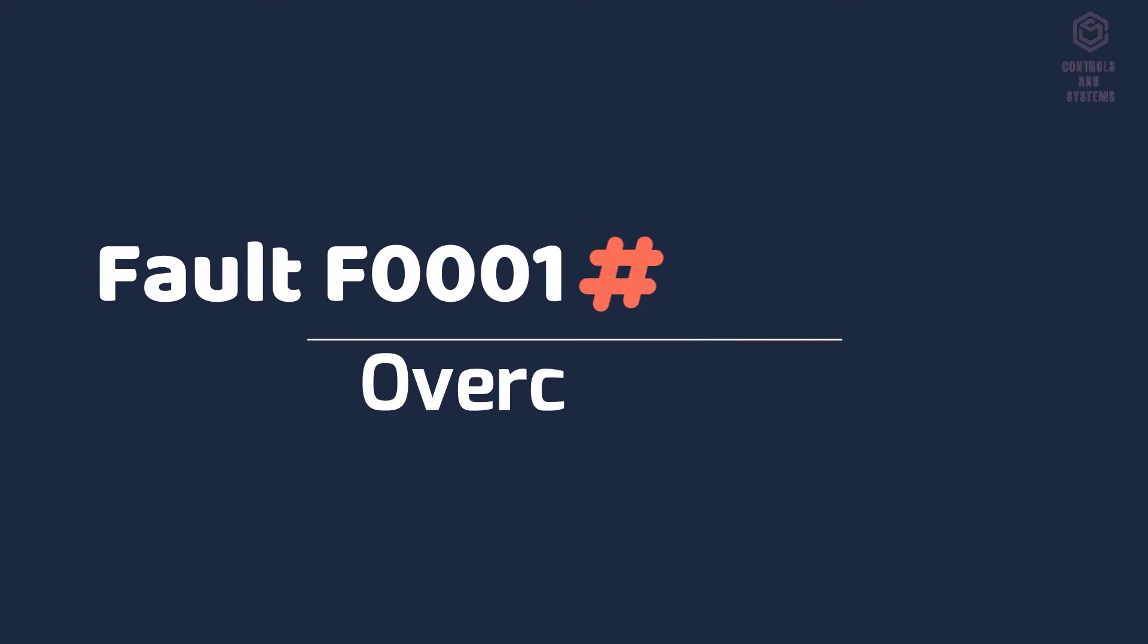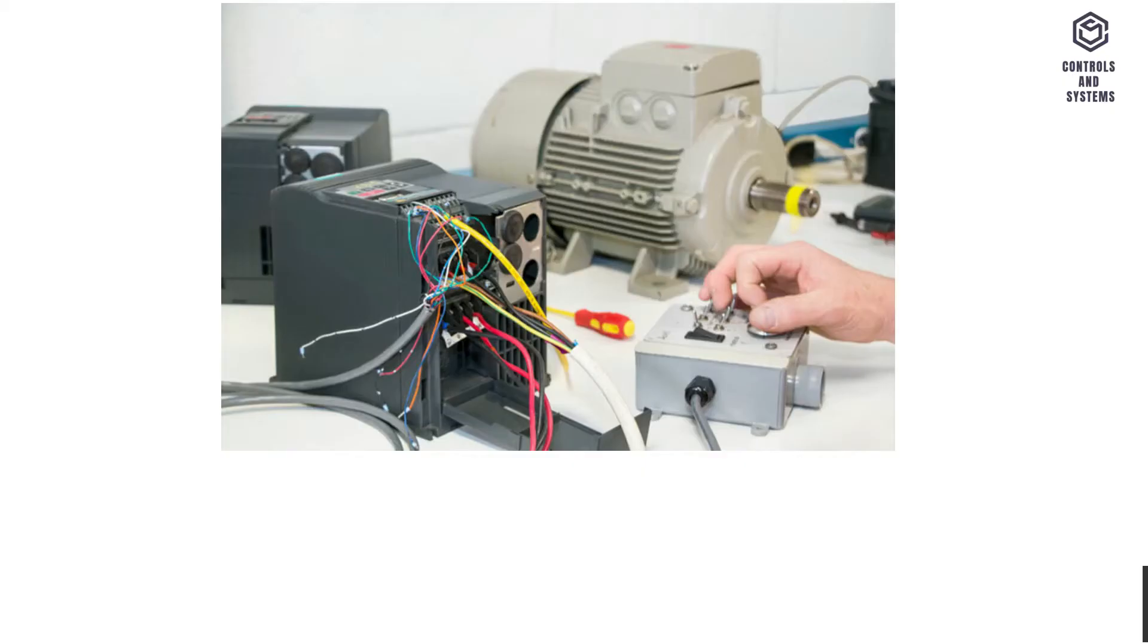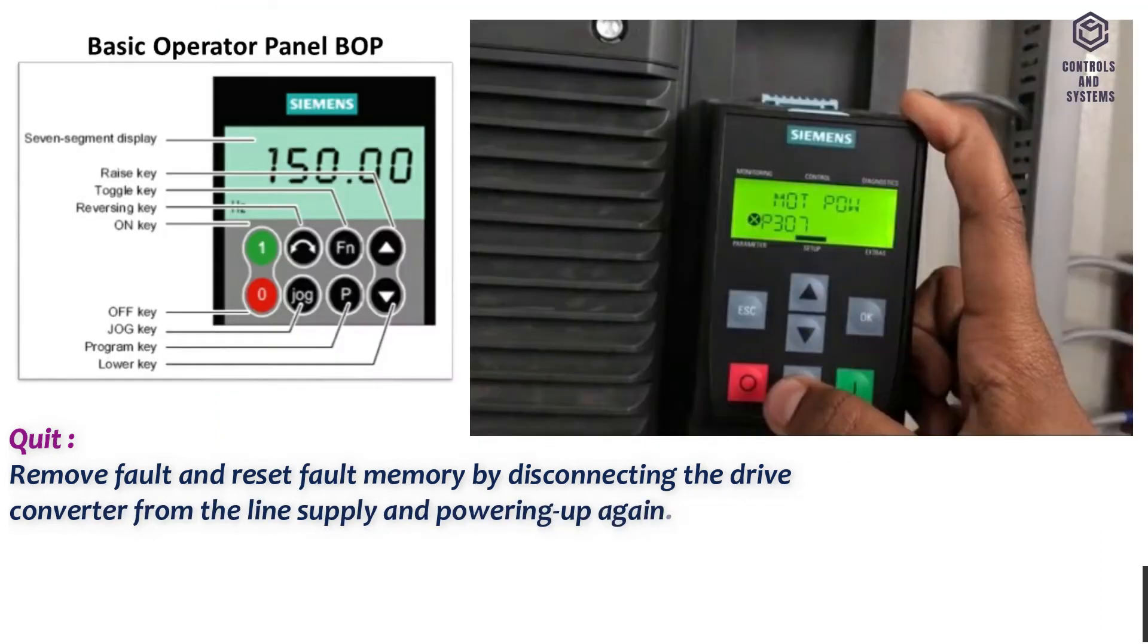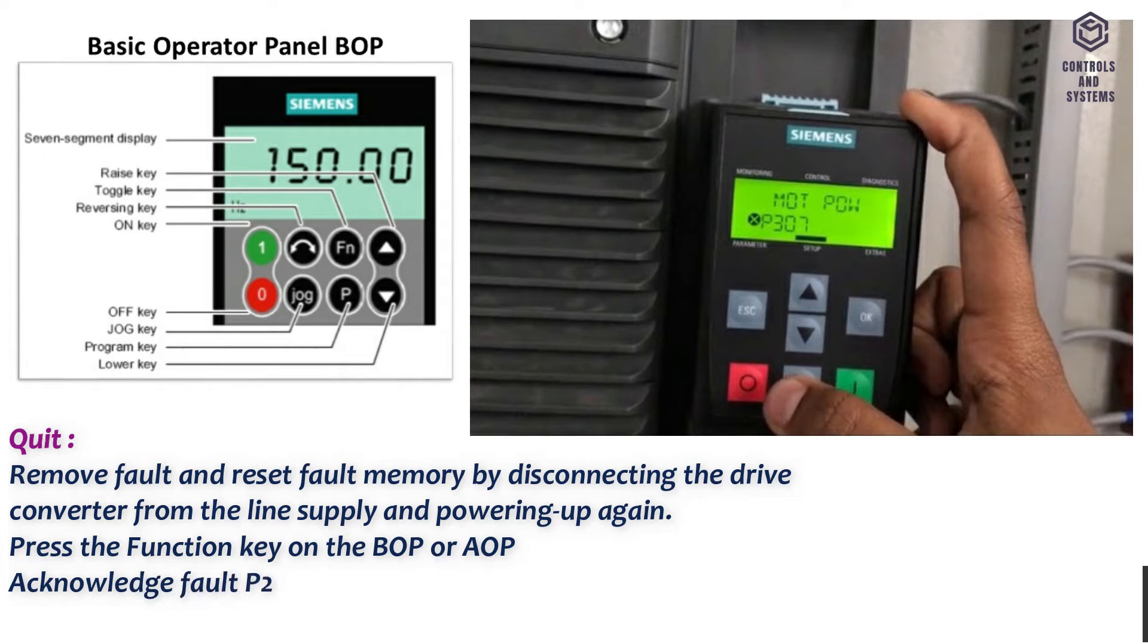Fault F0001, overcurrent. Quit: Remove fault and reset fault memory by disconnecting the drive converter from the line supply and powering up again. Press the function key on the BOP or AOP. Acknowledge fault P2103, P2104, P0952, complete fault memory.